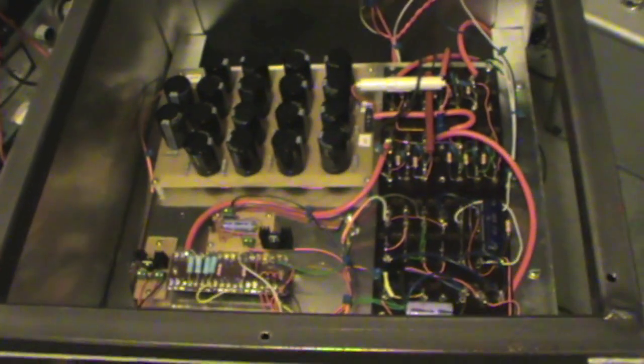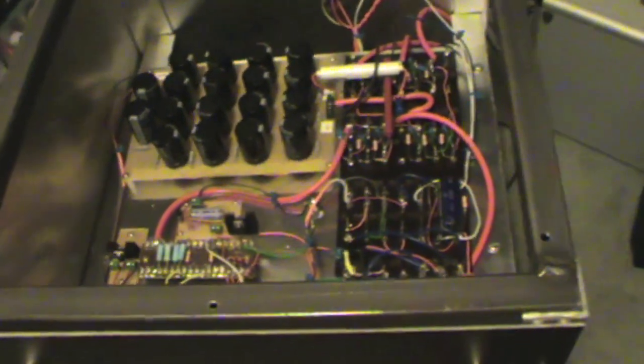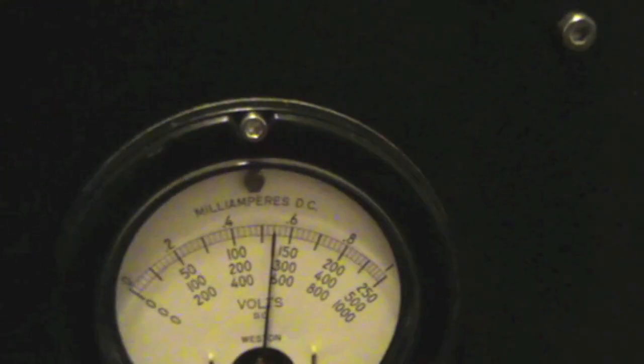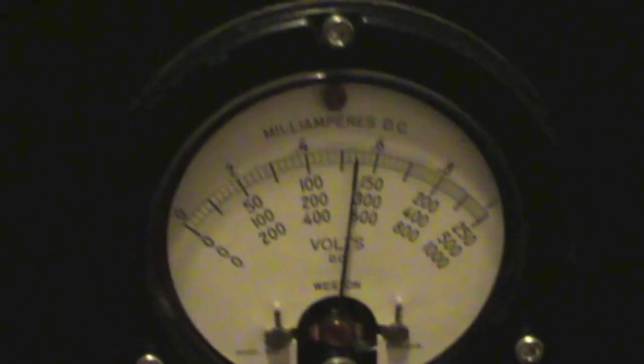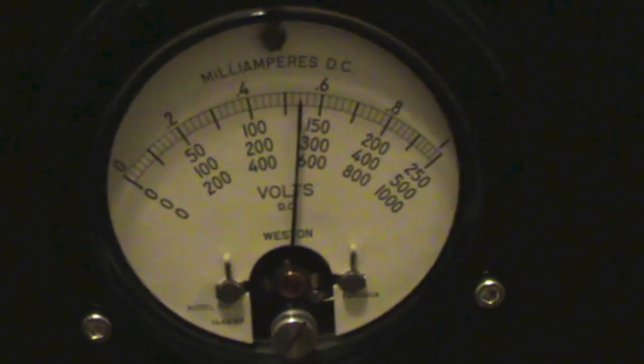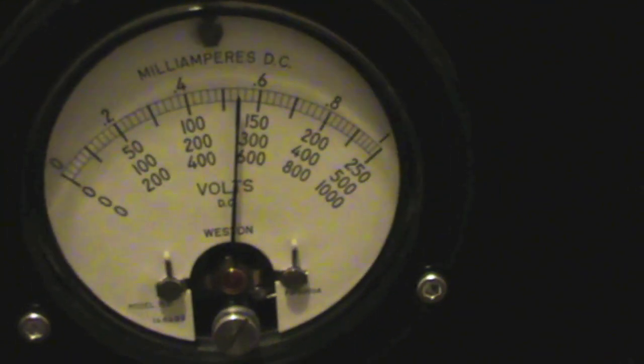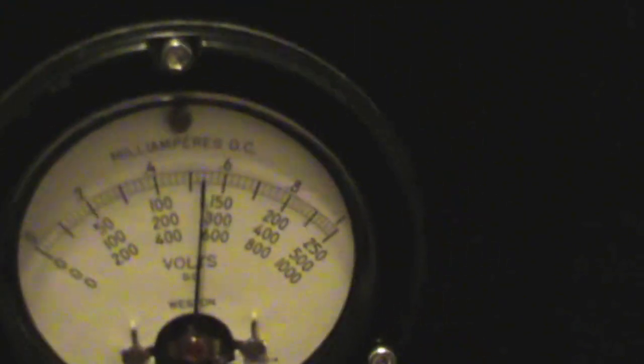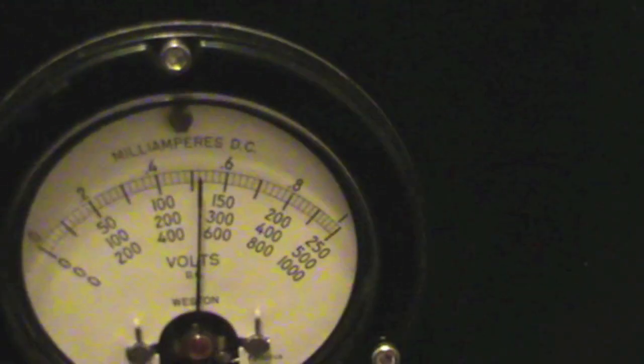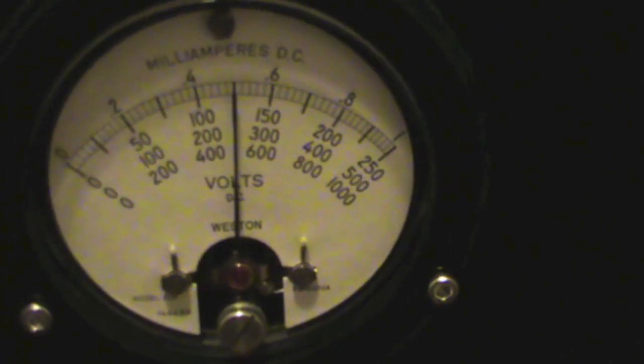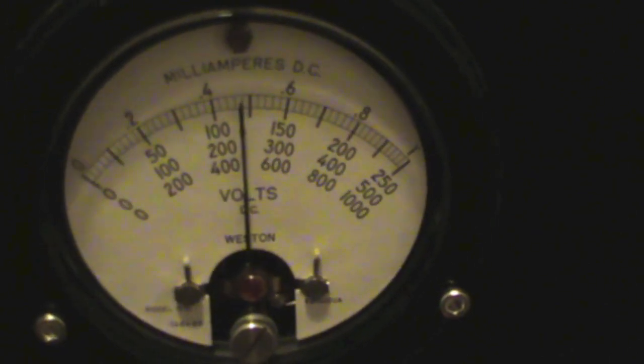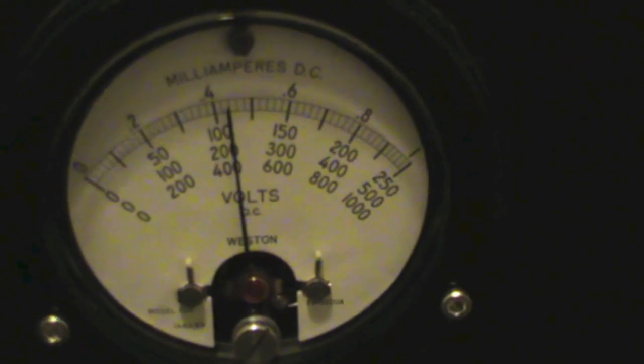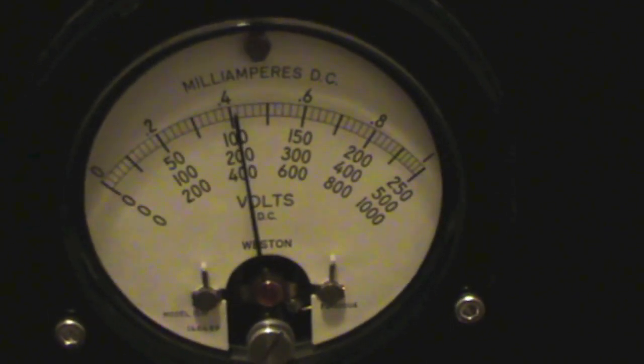So you steer well clear of it. Coming back to the meter, when I switch it off, you'll be able to see... zoom in there. You should be able to see the voltage drop as the bleeding resistors on the capacitors take over. There we go, the voltage slowly dropping off.